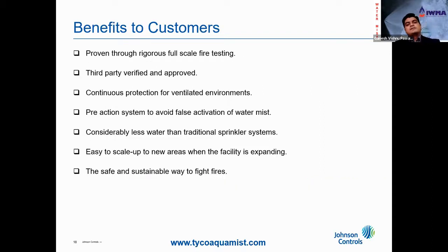So what are the benefits of using the water mist system? First of all, the water mist system is proven through rigorous full-scale fire testing by FM. It is a third-party verified and approved system. We need not shut down all the ventilation units, and the data center has continuous protection for ventilated environments. Pre-action systems are used to avoid the false activation of a water mist system.